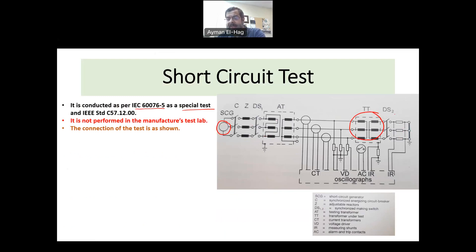Now, we have here the short circuit on the transformer, and there is a switch DS2. And we have a switch DS1 that is at the generator side. One of those switches will be normally closed before starting the test. So there are two different methods. One method is to connect the short circuit before starting the test, and then you close DS1 to generate the short circuit.